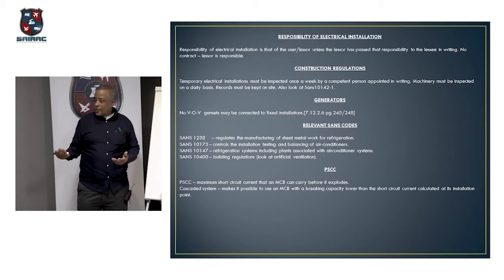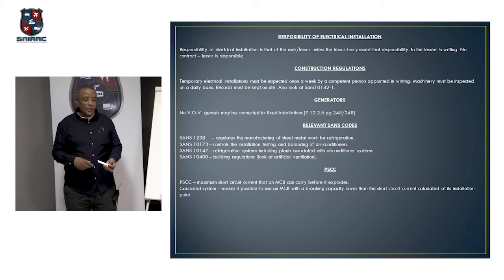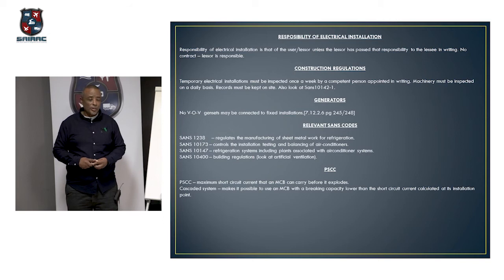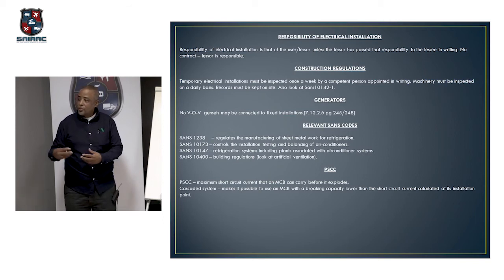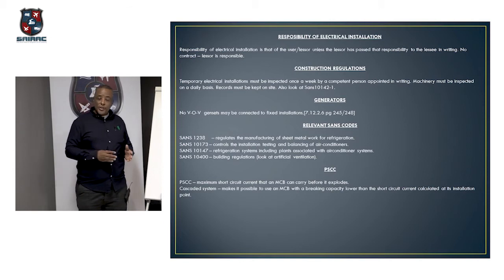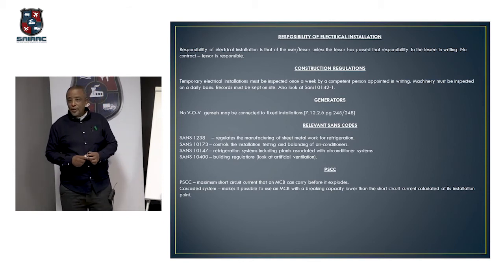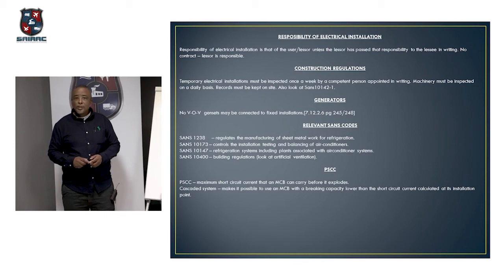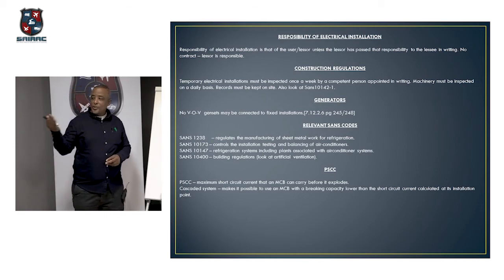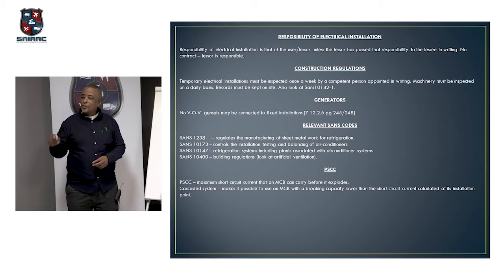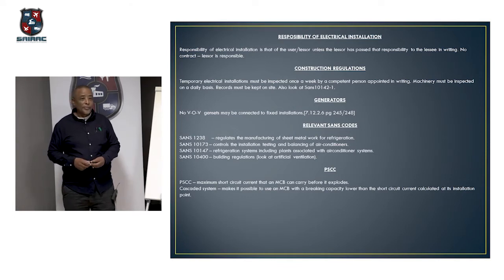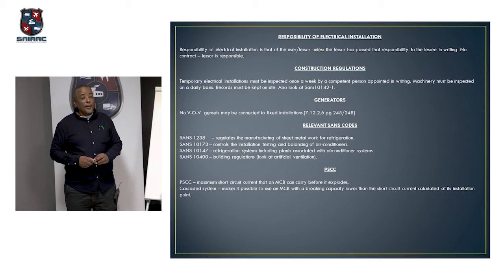Generally, on a normal installation, you can measure your PSCC with a meter, and it'll tell you what it is. Some guy phoned me and asked, what should the reading be? I said, don't ask me that question, you should calculate it. Generally, those instruments can only do up to about 100 amps. Anything over and above, you need to calculate it. There are graphs, and consultants and engineers just use programs to calculate it. 5 kA seems to be a very general figure. He asked me, will 5 kA be right? I said, don't ask me to commit myself, do the calculation.